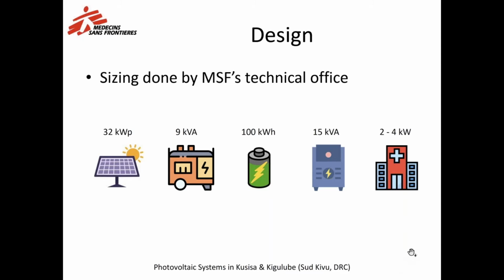So we went for 32 kilowatt peak photovoltaic modules. Each hospital had 2 generators of 9 kVA each, which were only acting as a backup power source. We installed a 100 kilowatt-hour battery bank and a 15 kVA charger inverter. All this system is for a hospital that is consuming between 2 and 4 kilowatts. The consumption is quite stable, it doesn't change much. It increases a little bit during the night due to the security lights, but it's around these numbers.